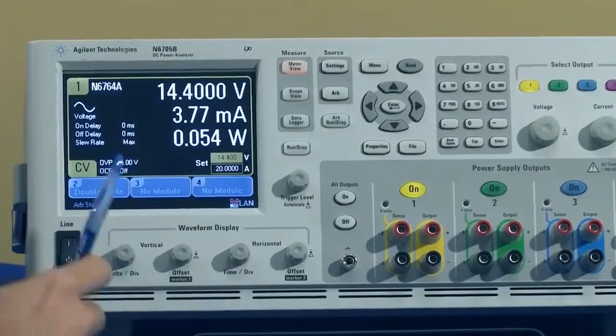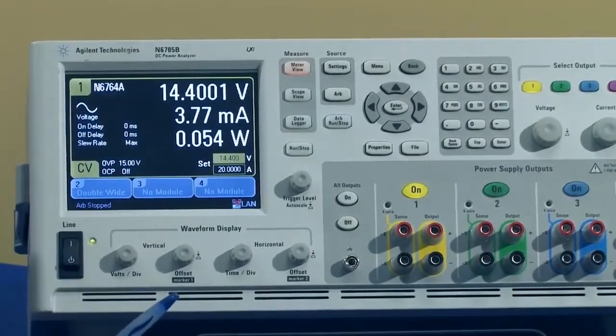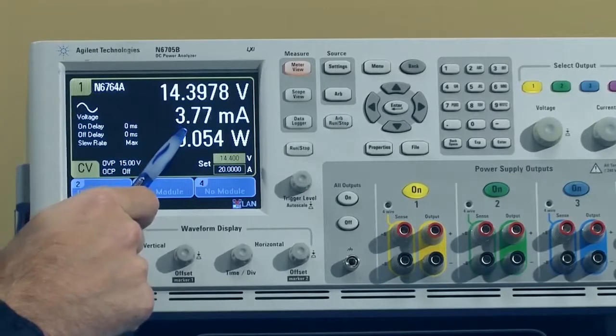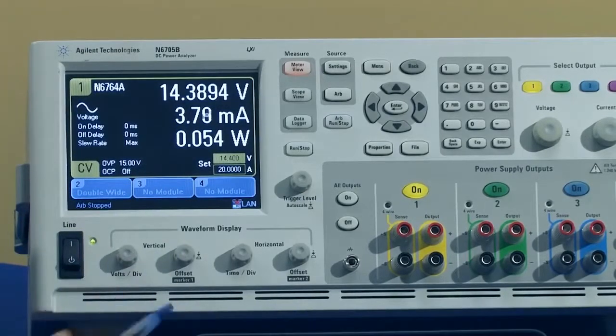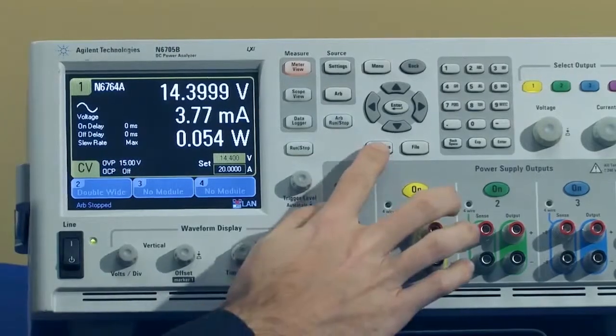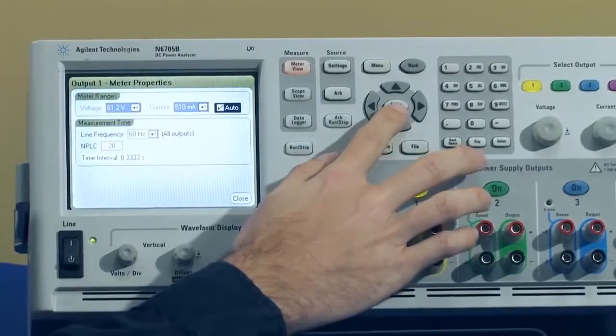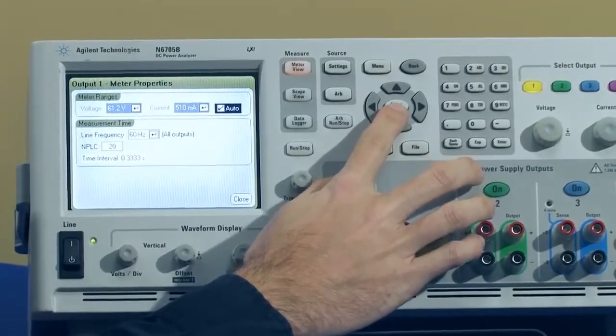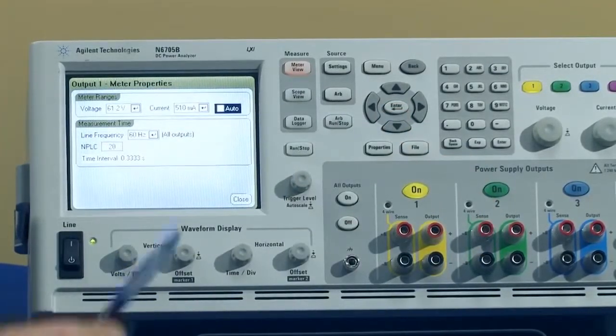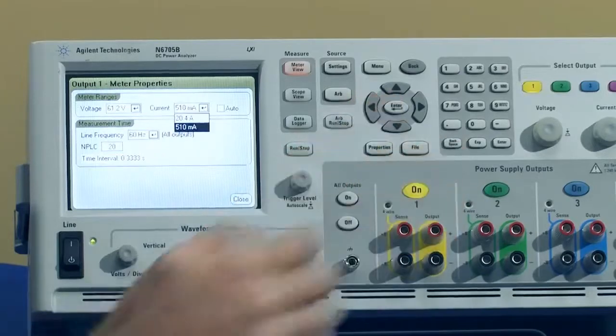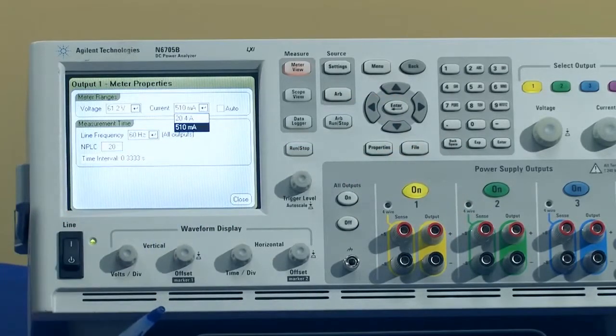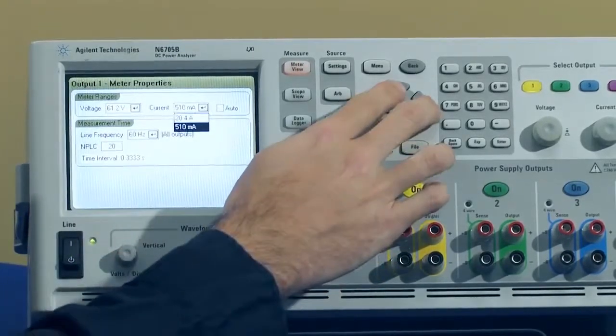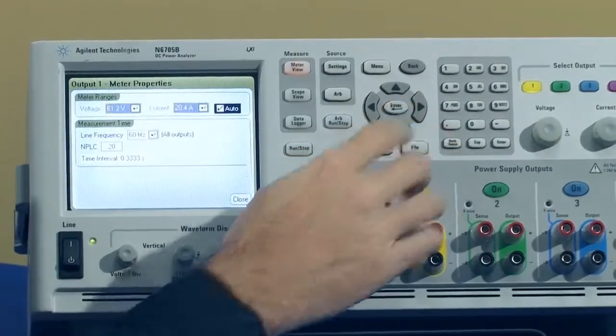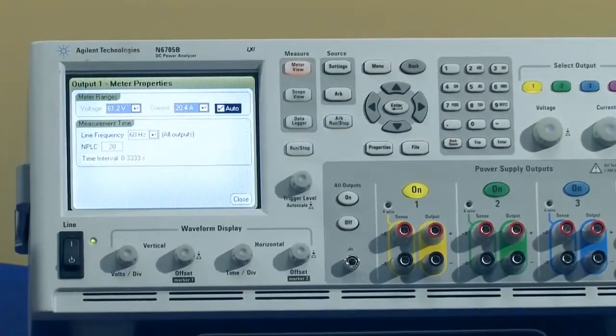I mentioned that this particular module has 2 built-in measurement ranges. In order to get this very accurate, almost 4 milliamp measurement, we're actually in the lower measurement range. It's easy to change ranges just by going into the properties section, and right now I have it on auto, meaning the range will be chosen automatically by the module depending on the output current. You can see the other 2 ranges are 20 amps as well as 500 milliamps, so depending on the accuracy you need, you can choose the appropriate range. I'm going to turn it back to auto because we'll be going much higher than 500 milliamps.